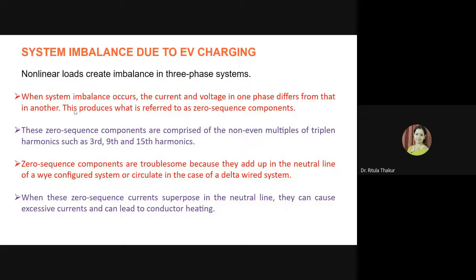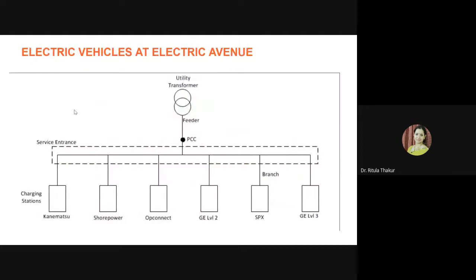And why are these zero sequence components troublesome? Because they mainly add up in the neutral line. So suppose we are talking about a star connected system, these zero sequence currents superimpose in the neutral line and cause excessive currents and lead to conductor heating. And in the case of a delta system, they just circulate. So again, this system imbalance due to EV charging is one major cause of worry.